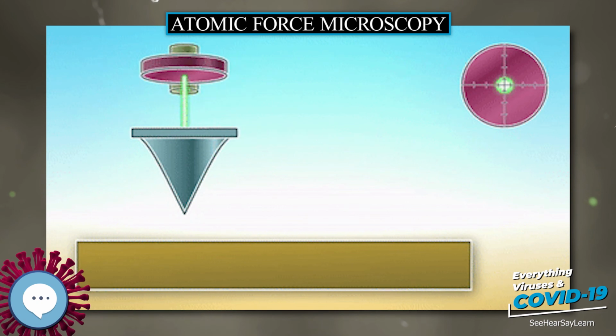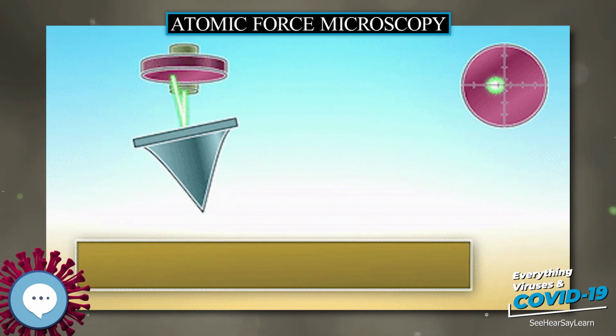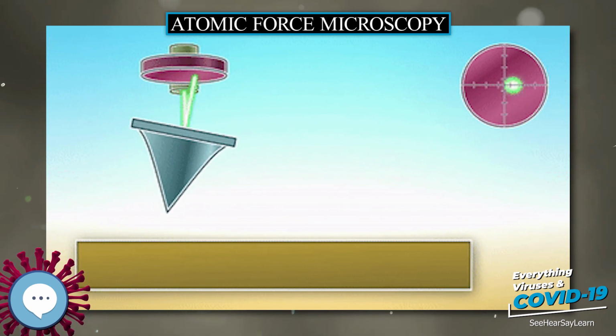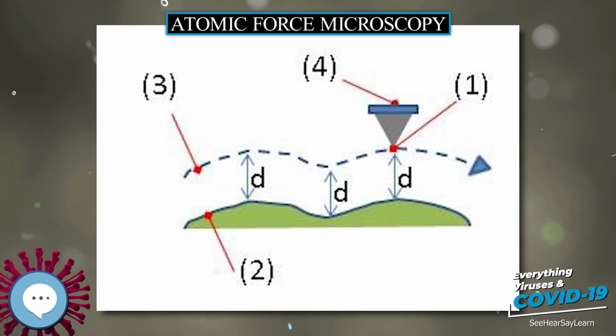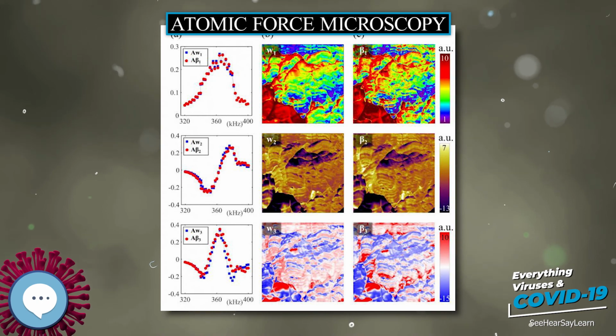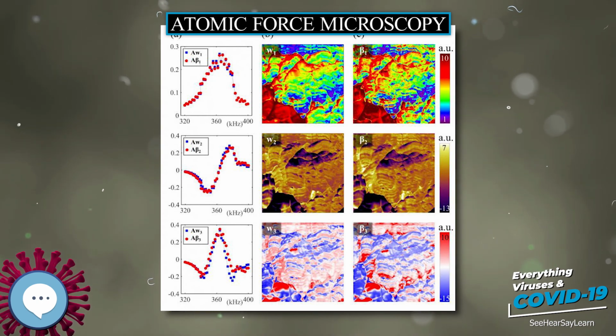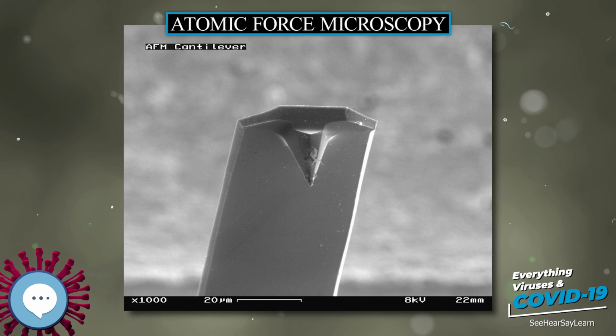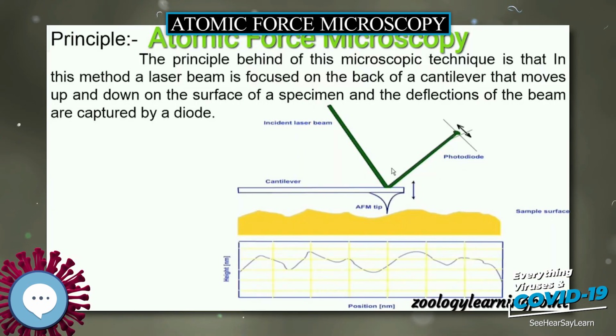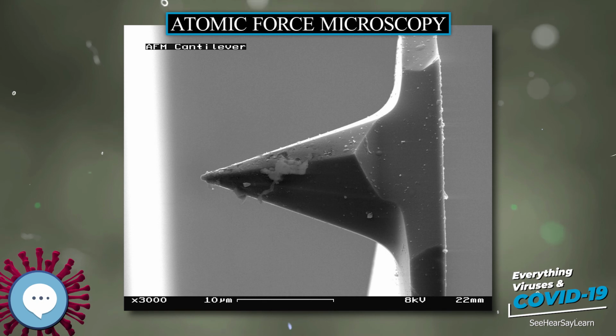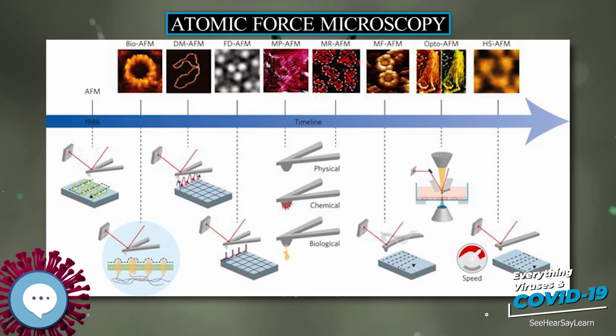An AFM probe is a particular type of SPM, scanning probe microscopy, probe. AFM probes are manufactured with MEMS technology. Most AFM probes used are made from silicon, but borosilicate glass and silicon nitride are also in use. AFM probes are considered consumables as they are often replaced when the tip apex becomes dull or contaminated or when the cantilever is broken. They can cost from a couple of tens of dollars up to hundreds of dollars per cantilever for the most specialized cantilever/probe combinations.